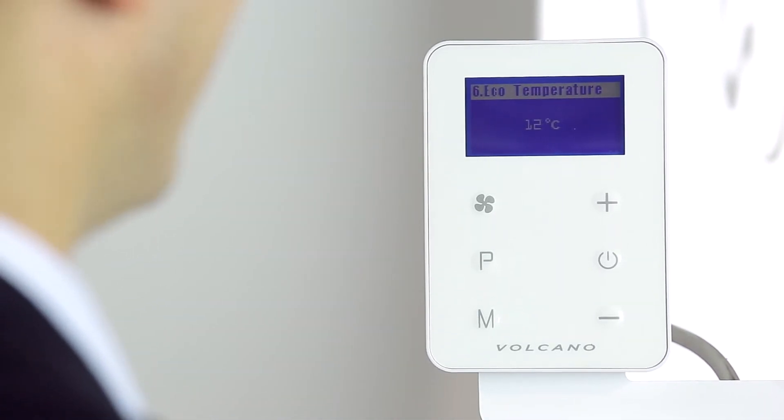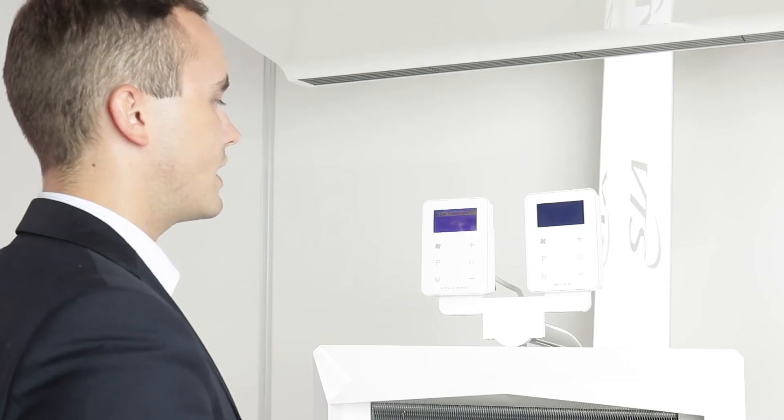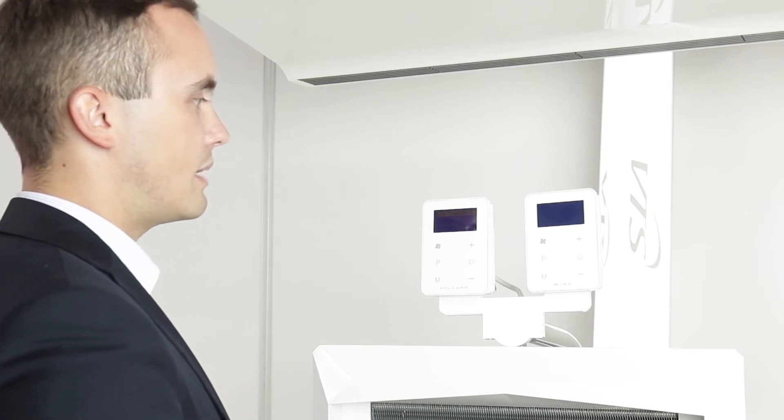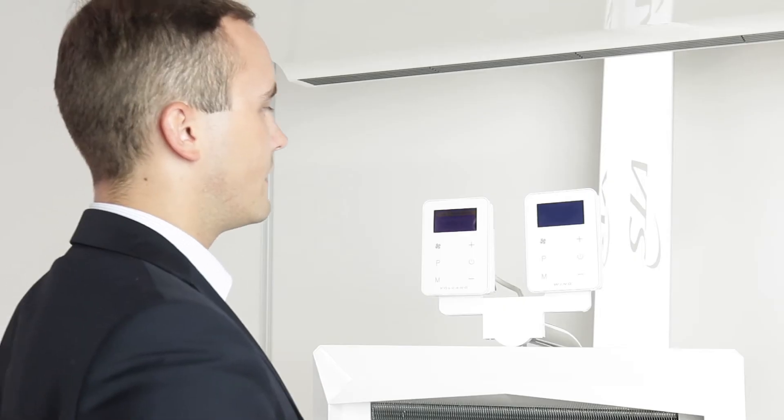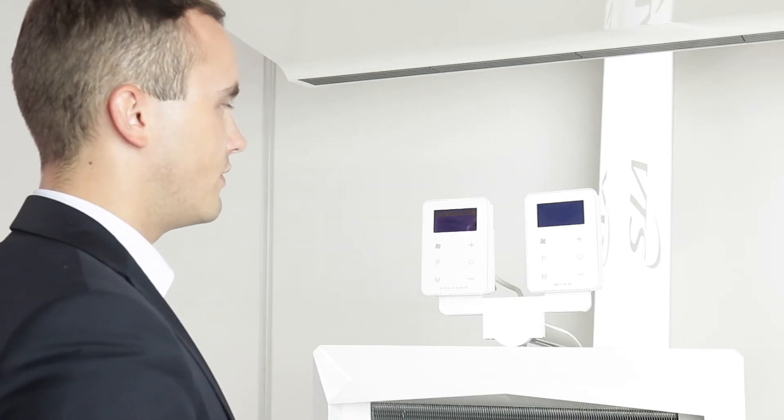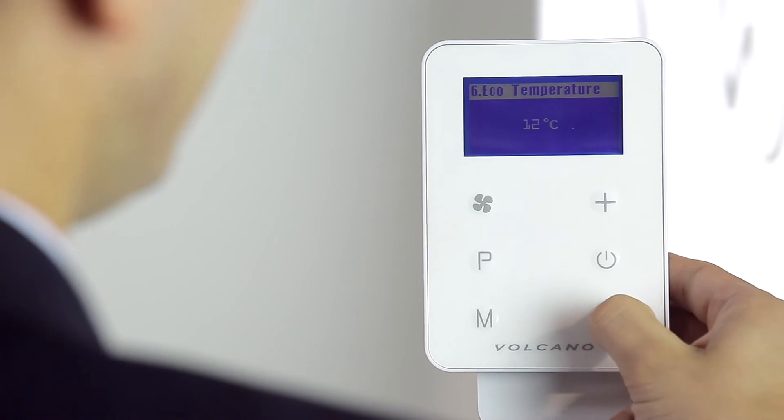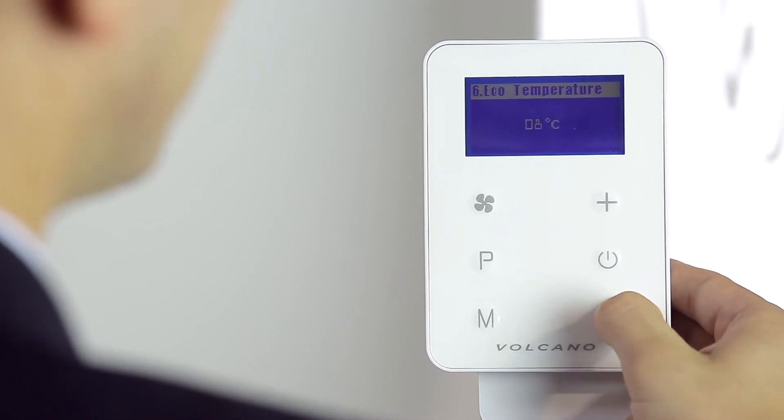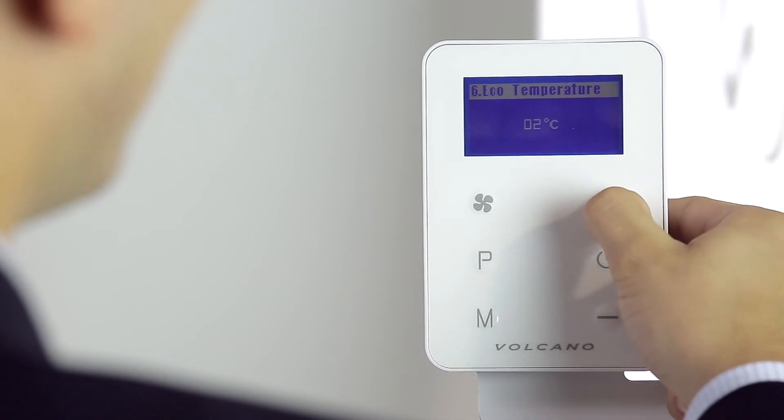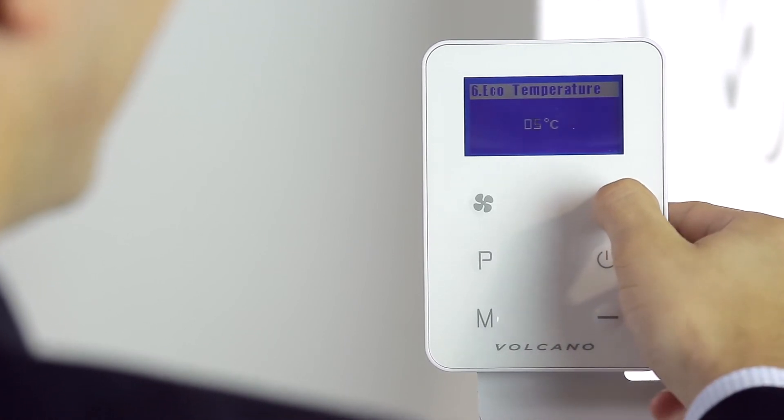The Volcano EC controller gives us the possibility to also set the economic temperature which will be set outside the programmed heating periods and also gives us the possibility of setting the anti-freeze temperature. We have a choice between 2 and 22 degrees celsius and this will be our set temperature for the economy mode and for the anti-freeze protection of the heat exchanger.